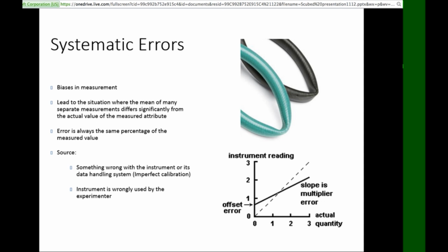It is very important that measuring instruments such as ammeters and voltmeters are checked periodically against known standards. Finally, systematic errors can also be detected by performing experiments using different procedures and comparing results. It's not always possible to reduce the systematic error. However, if the magnitude and direction of the error is known, the accuracy can at least be improved by additive corrections or proportional corrections.